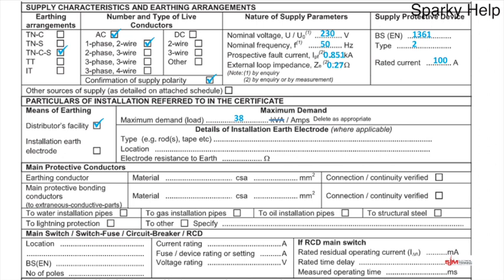My conclusion would be, based on your assessment or the assessment that the inspector has done, that the incoming supply is not big enough, and therefore I would have to go back to the electricity company, or send the client back to the electricity company, to get an upgrade of supply. So beware of that. It's not supposed to be a transfer of the fuse rating down here, because very rarely is the maximum demand that high relative to the rated fuse. You're basically saying it's at maximum capacity. It's surprising how little we actually use.